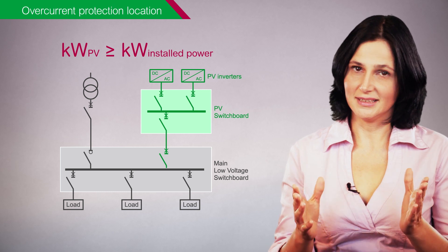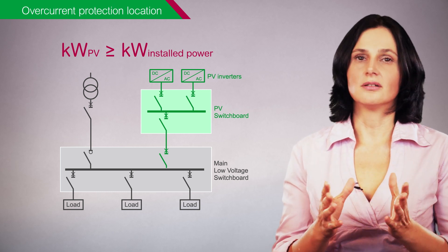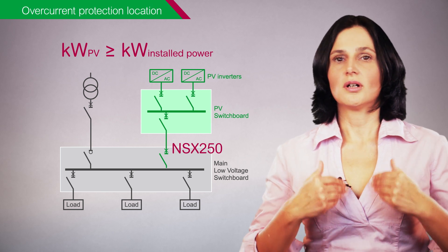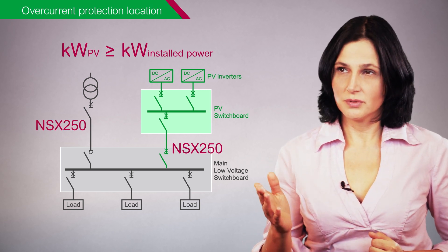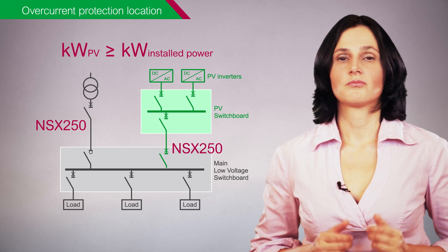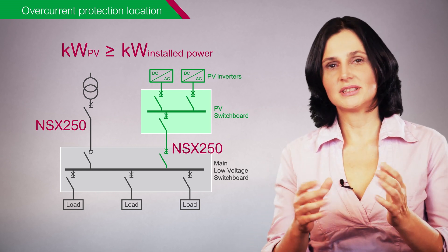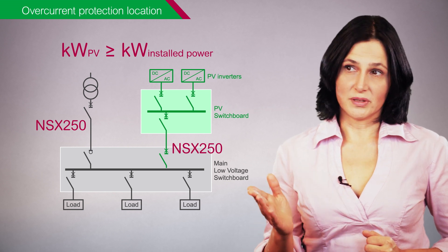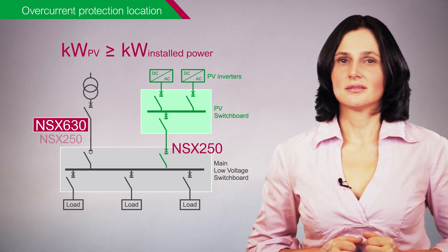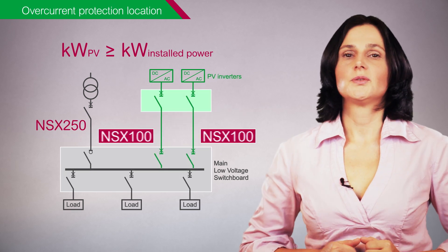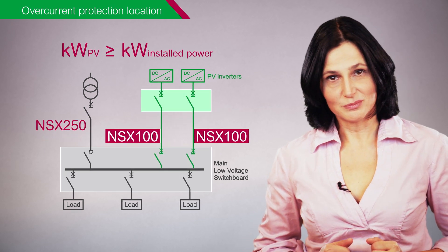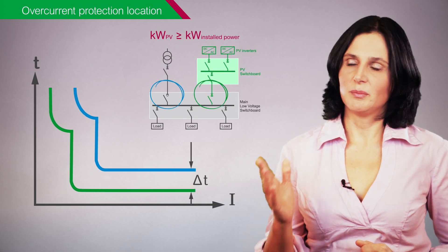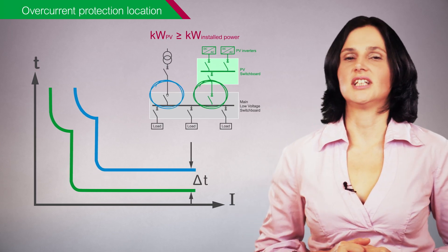In this case, the circuit breaker at the photovoltaic incomer has the same rating or higher than the main circuit breaker, as shown in this example. Thus, to ensure selectivity between the two breakers, you may oversize the main circuit breaker, or split the photovoltaic system into smaller systems, or consider time selectivity for applications higher than 630 amps.